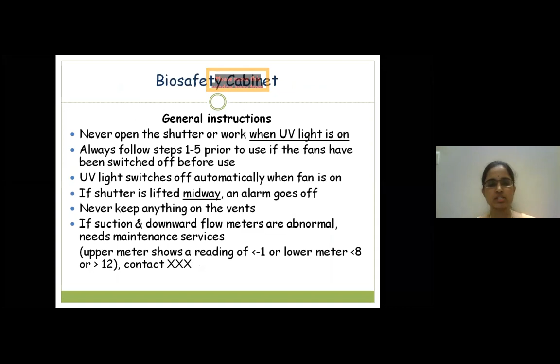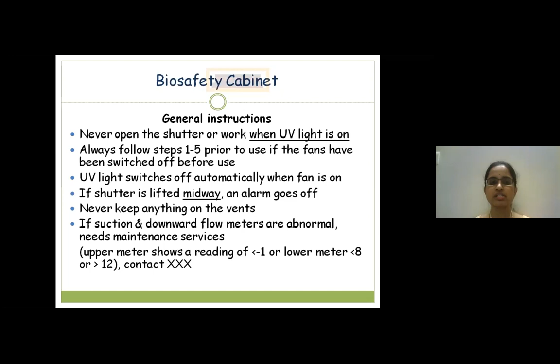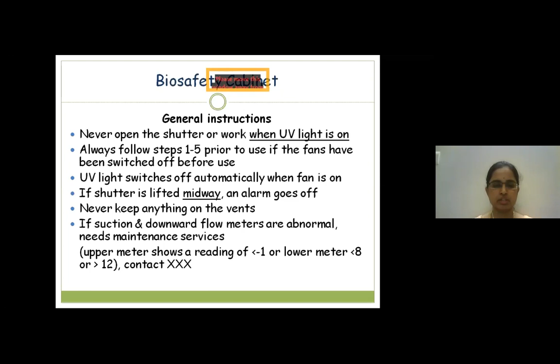There are standard operating procedures for usage of the biosafety cabinet. We do not need to know the details of these. We just need to know that it needs to be cleaned and exposed to germicidal UV light at least for 30 minutes, after which it is re-cleaned again. After use, the chamber has to be cleaned again to eliminate any spillage, and again exposed to germicidal UV light. Two important general instructions we need to know is that when the nurse is working with the equipment and drugs that are placed in the cabinet, the shutter is never lifted beyond midway, following which an alarm goes off and the procedure has to be stalled. Also, when the UV light is on, we should never open the shutter.